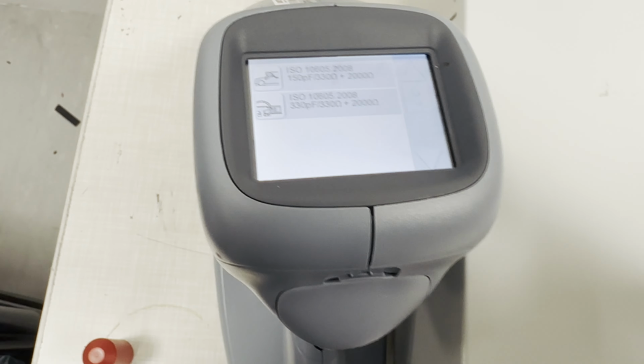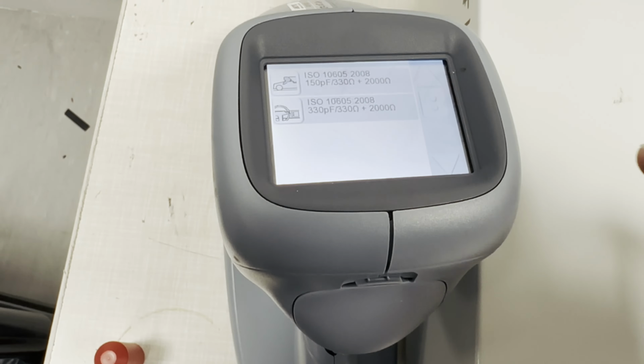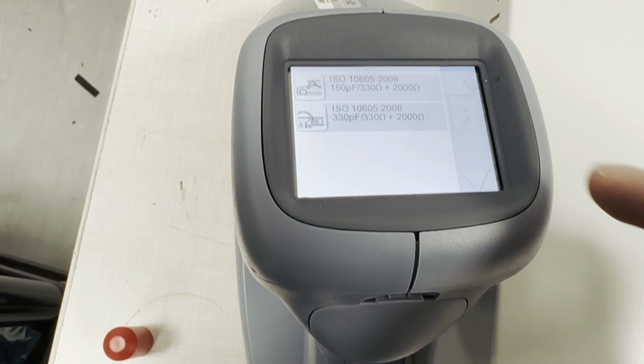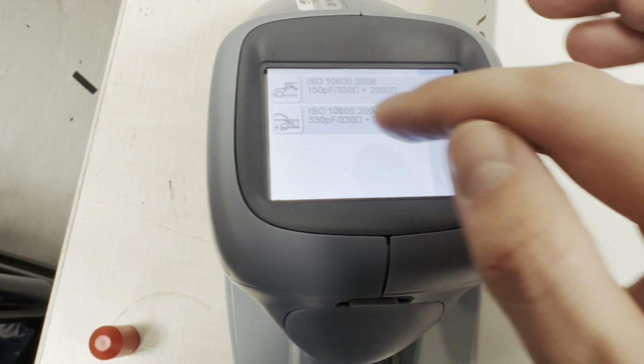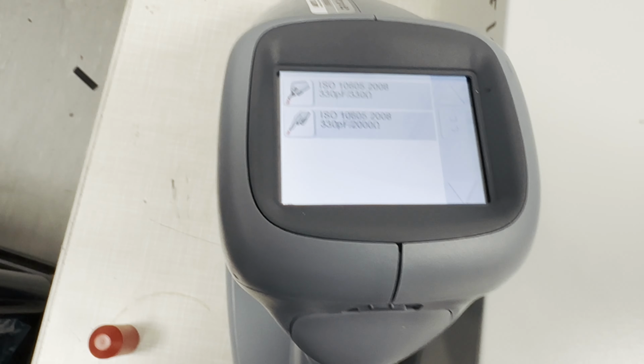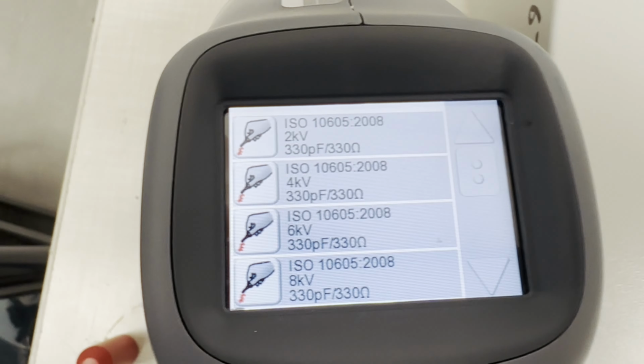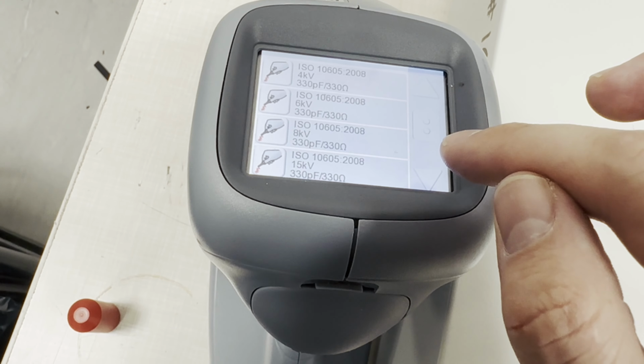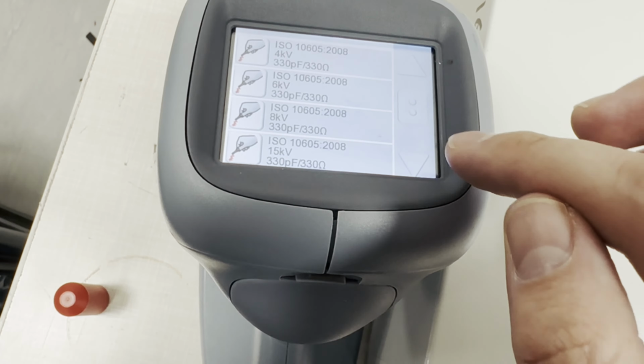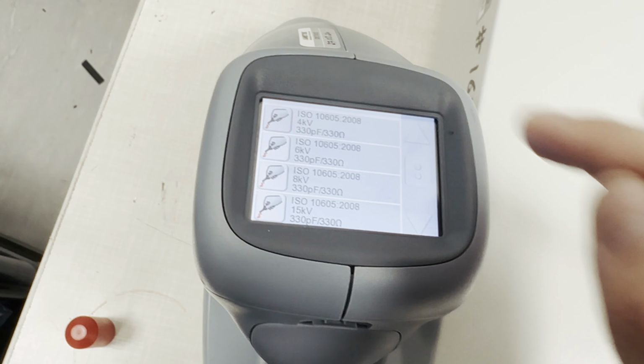So we're going to select ISO, and I always go with the default probes, but you have a couple of options here, so you can see where it's applying. We're going to go with the second option because we're testing electric equipment inside the vehicle, not outside. Then we're going to pick the lowest resistance, and finally we get to the actual voltage. We typically start with 4 kilovolt. I'm not sure why 2 kilovolt is listed, but it's not necessary. And then you can see that it goes up to 15 kilovolt. Actually, the test allows you to do even more, but for contact, we don't have to do more than 15 kilovolt. So we're going to start with 4 kilovolt.